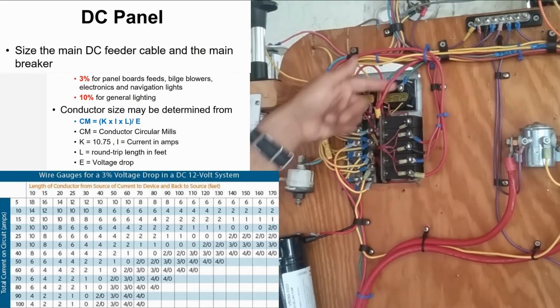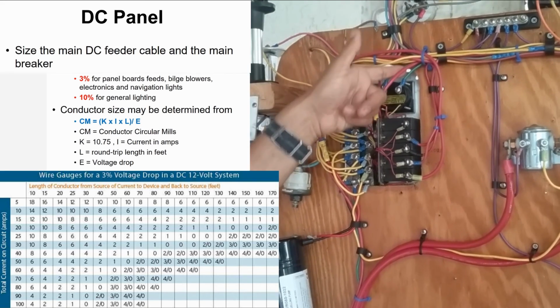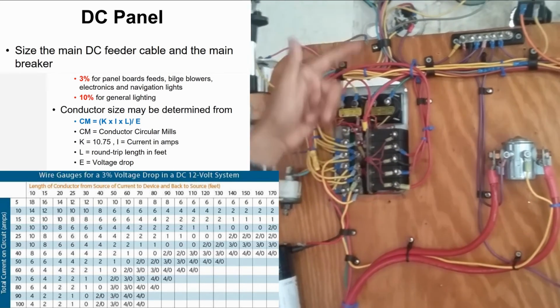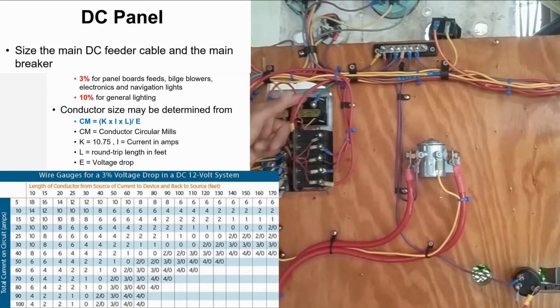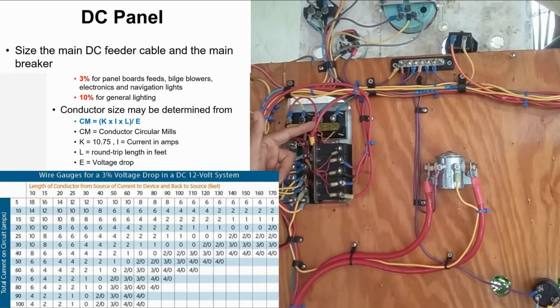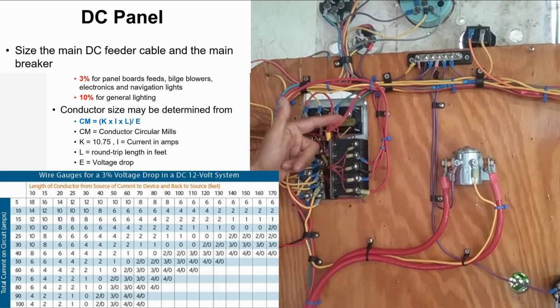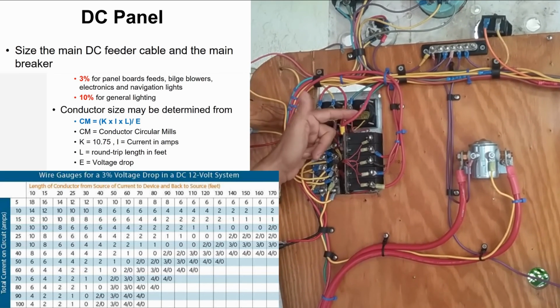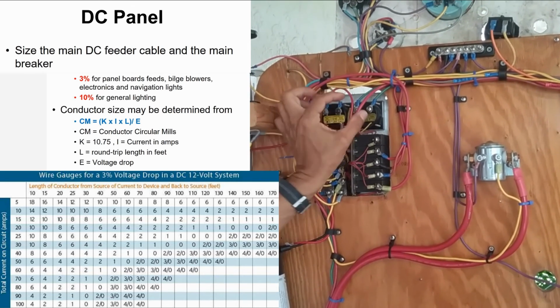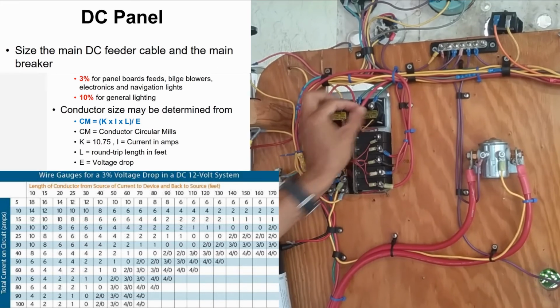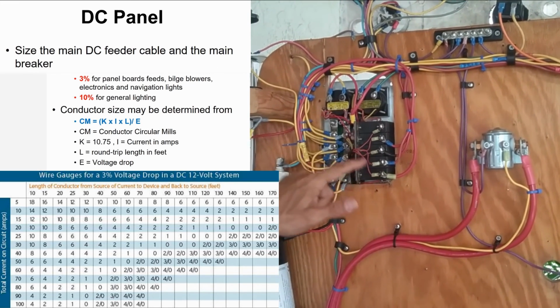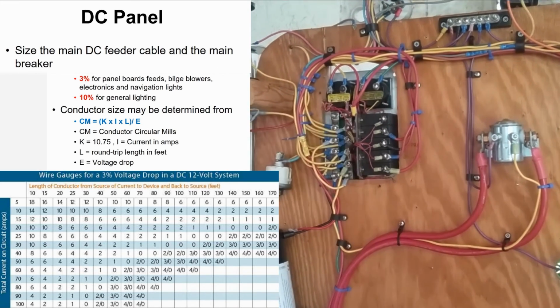That cable is coming from the positive of the switch selector, from the battery switch selector in the output. You need to calculate the gauge of this wire according to the amount of breakers and the capacity of the breakers.